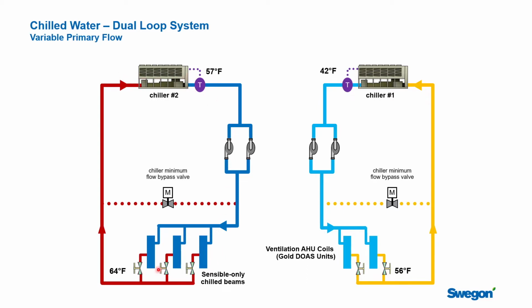And having a dedicated loop for the chilled beams, and then you have a second loop where we're going to make 42-degree water, and we're going to send that water out to the air handling units. It's going to have to be in that 42 to 44-degree range because we have to do all the dehumidification for the whole building down in here.